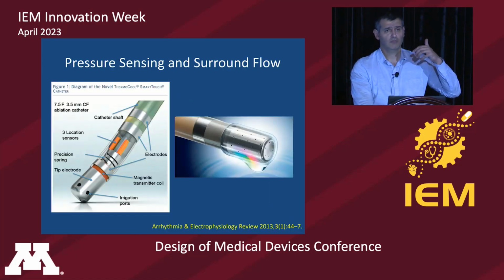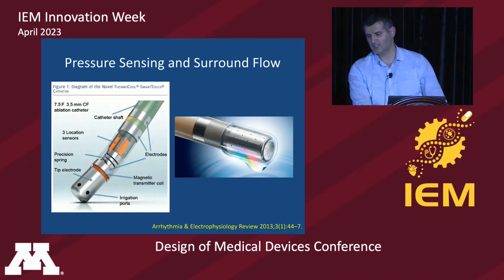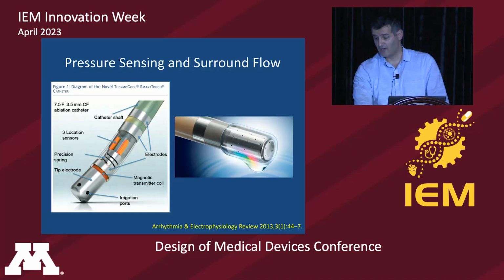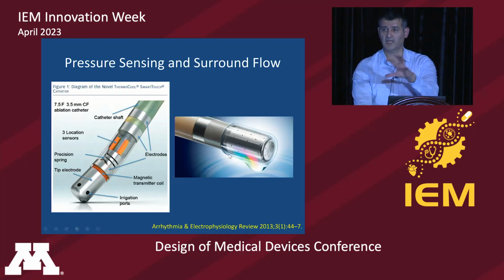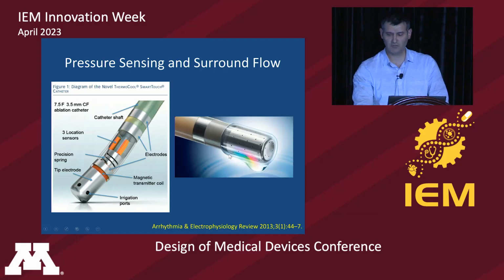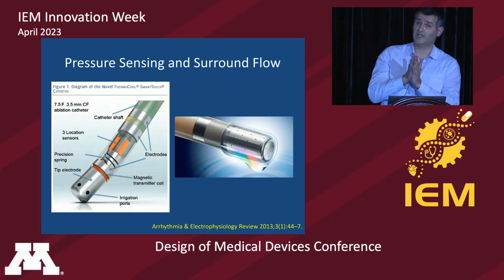Now, after irrigation came more and more advancement to the RF catheter. Now we have not just the irrigated tip. Now there are multiple holes to uniformly irrigate the tip of the catheter and the surrounding tissue, rather than just 6 holes, up to 64 holes on a tip. That's what we call surround flow catheters. The tip also has an integrated pressure sensor and directionality sensor.